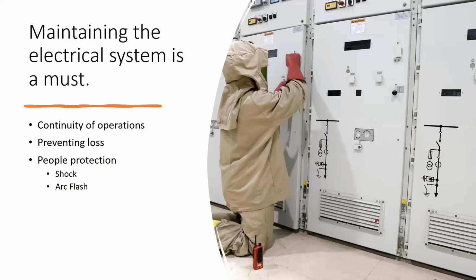And every breaker is different depending on the size of it. People think that a breaker opens, it just kind of opens instantly, but the reality is there's moving contacts, there's moving parts. All those parts have mass to them. And from a mechanical standpoint, even whenever the breaker's got the signal to open, it takes time to get that mass moving and get those contacts open and get the arc out. And that all may happen in a cycle, which would be 16 milliseconds.